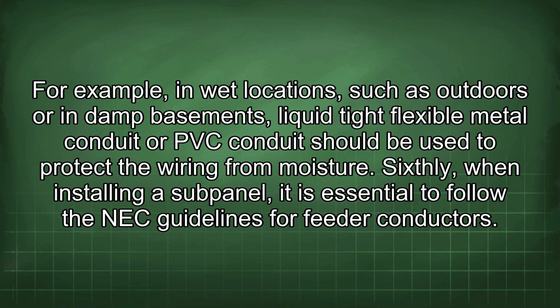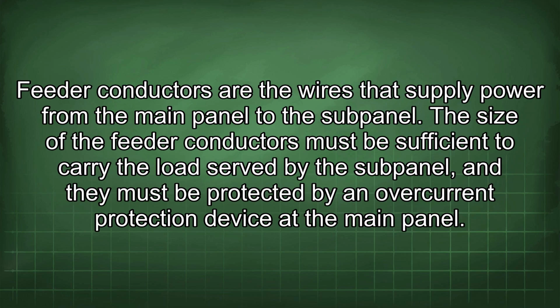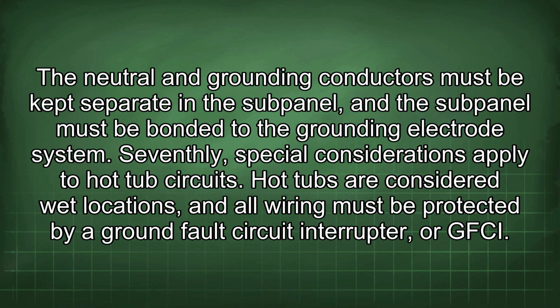Sixthly, when installing a subpanel, it is essential to follow the NEC guidelines for feeder conductors. Feeder conductors are the wires that supply power from the main panel to the subpanel. The size of the feeder conductors must be sufficient to carry the load served by the subpanel, and they must be protected by an overcurrent protection device at the main panel. The neutral and grounding conductors must be kept separate in the subpanel, and the subpanel must be bonded to the grounding electrode system.